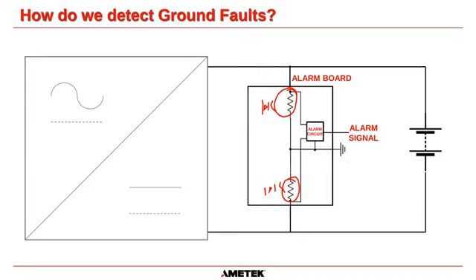And then that goes into an op-amp circuit, which basically uses a ground as a reference, and it will monitor whether these points here are where they should be away from ground. And if one of them tends to go towards ground, then you'll get an alarm signal out, and it will either show you on a display. It could be a lamp. It could go to your DCS system. But we don't use lamps anymore. We use a more complex alarm board circuit.